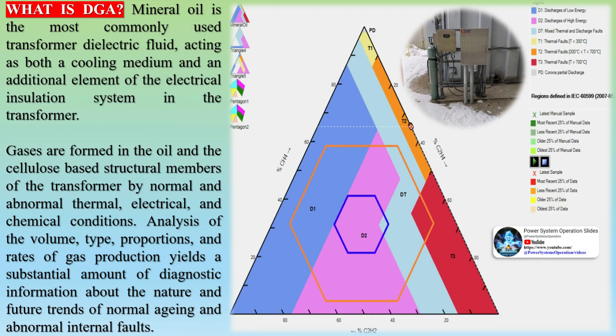In addition to the gas levels, DGA interpretations are based on a large number of variables, such as equipment type, liquid type, past history, history trending, manufacturer, equipment age, voltage, gallons, breather type, temperature, and service history, among others.